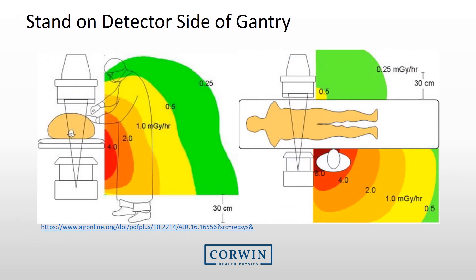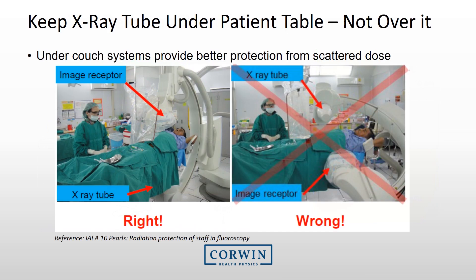This is outlined in the scatter plots on this slide. There are much higher exposure rates on the tube side of the patient than on the detector side. Therefore, it is recommended that the tube always be kept below the patient instead of above. Under-table systems provide better protection from scattered radiation than over-table systems.